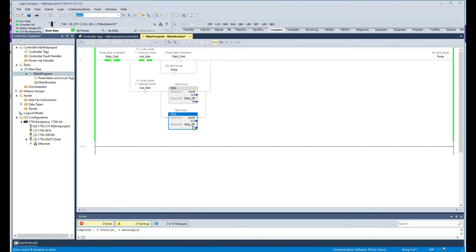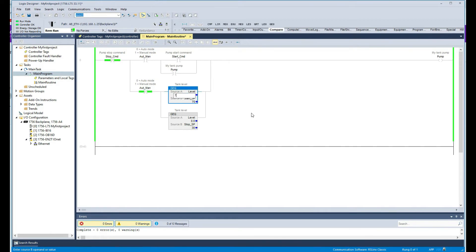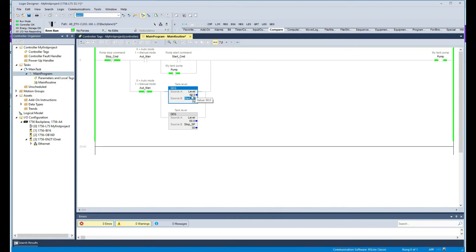Right now my level is zero, so if I go to auto mode the pump does not start. I need to be above 70 percent. If I put a value of 75, the pump starts. As we simulate the level dropping — to 60, then 40, then 30 percent — the pump stays on. But as soon as I go below 30, the pump stops.